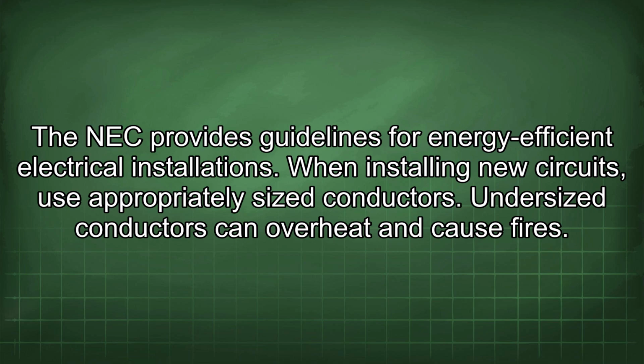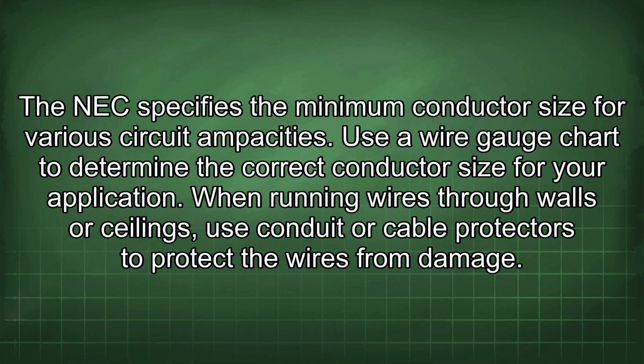When installing new circuits, use appropriately sized conductors. Undersized conductors can overheat and cause fires. The NEC specifies the minimum conductor size for various circuit capacities. Use a wire gauge chart to determine the correct conductor size for your application.